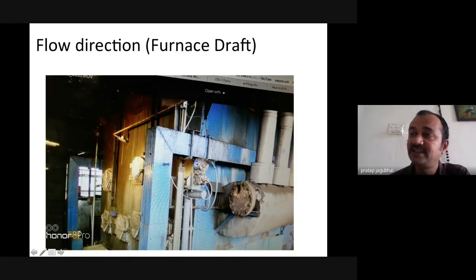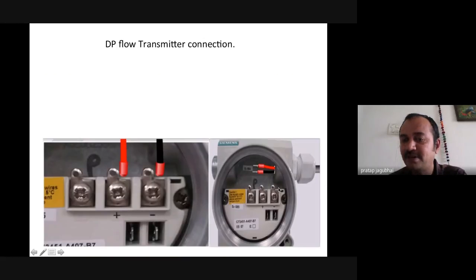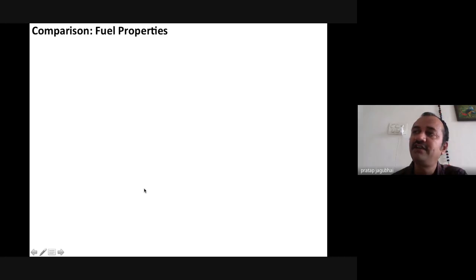Another important measurement parameter is draft, to balance the mechanical balanced draft, FD and ID. The draft pressure transmitter is to be put at 800 mm to 1 meter height from the base plate. This is the boiler front door, where you can sense through the DP pressure transmitter. The DP pressure transmitter is connected with a 2-core shielded cable, generally 0.5 or 0.75 square mm, and it can sense the differential pressure which we need to balance out, such that ID and FD can be balanced.